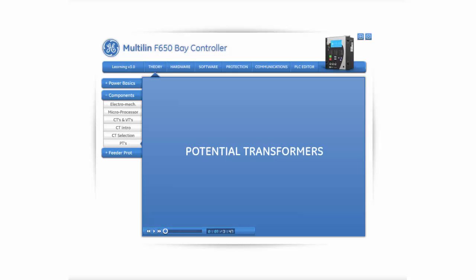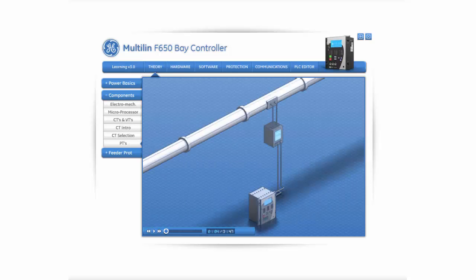Potential transformers. The next type of transformer we will cover is the potential transformer, symbolized as PT, or sometimes known as voltage transformers, symbolized as VT. Similar to current transformers, potential transformers scale down the voltage passed through them, as opposed to the previously mentioned current. The scaled-down voltage is then routed to a protective relay for measurement. Also as in current, a PT is classified with a conversion ratio indicating the amount the primary voltage is scaled down. For example, 60 to 1 scales a 7200 volt primary voltage down to 120 volts.